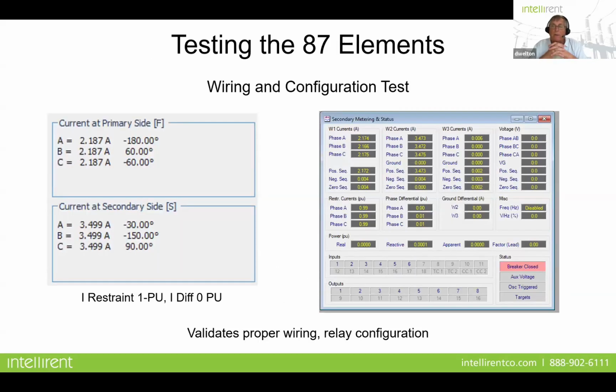Okay, let's talk about testing. The very first thing I do is what's called a sanity check. I'll take my test set, whether you've got a Doble, Omicron, or Manta, or whatever kind. To properly test a differential element, you need 6 phases of current. You can't just do it with 3. If you have 3 phases, the best you're going to do is minimum pickup, and you have to swap your test leads. So make sure you have the right equipment to test these relays.